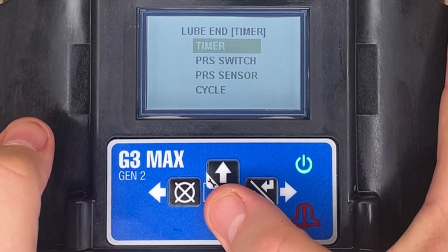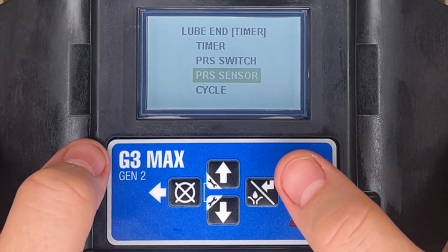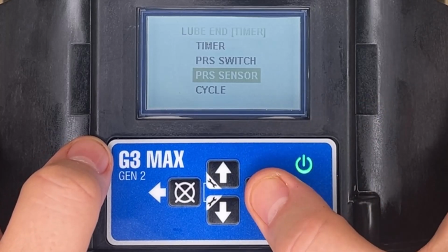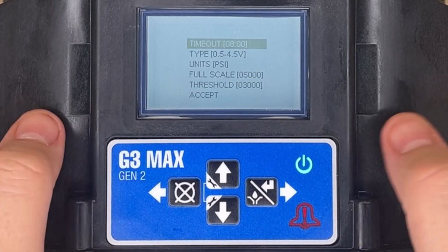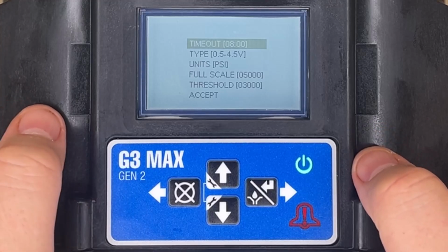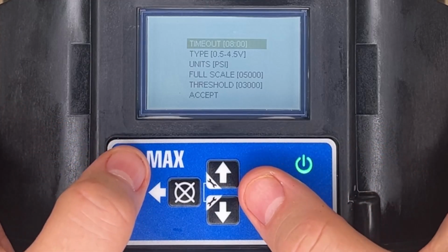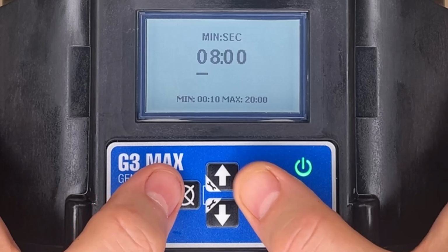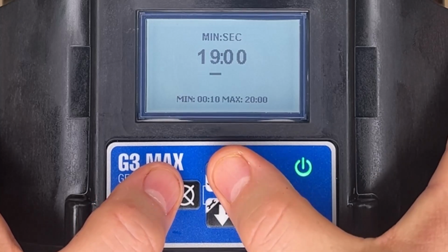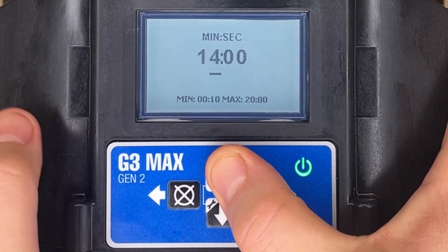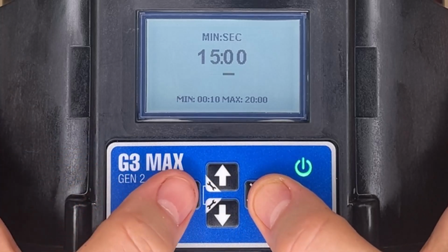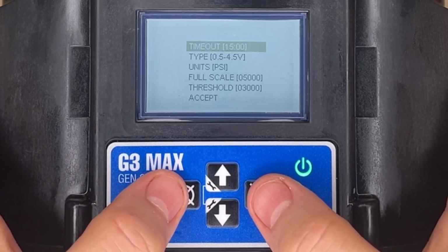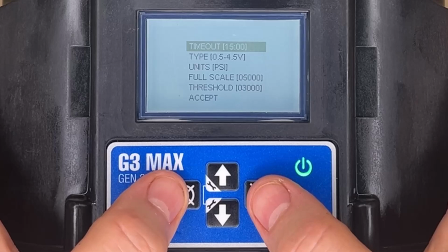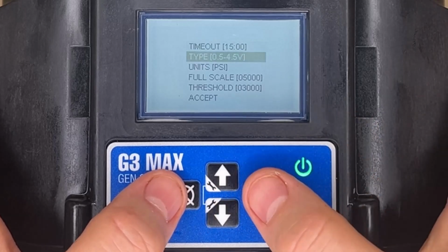So we're going to choose pressure sensor, and now there are a lot of details that we need to enter. The timeout time is about 1.5 to 2 times what we expect the system to require to fire the injectors. So let's say this is a big system that needs 15 minutes because we actually expect it to take about 7 or 8 minutes. Now the next thing to enter is the voltage setting of your transducer.